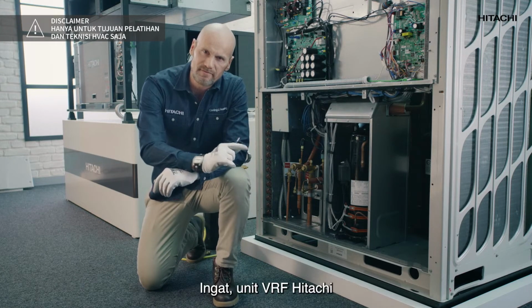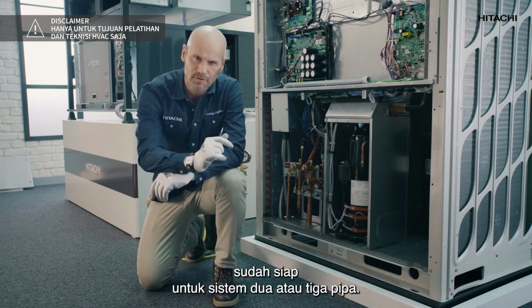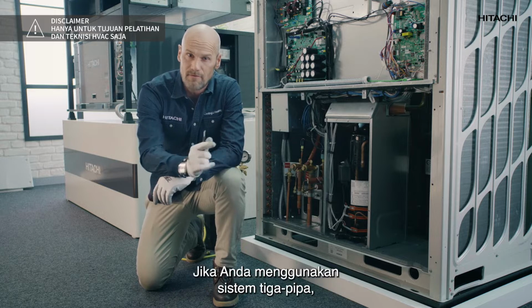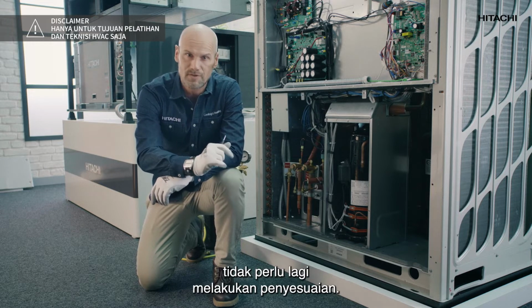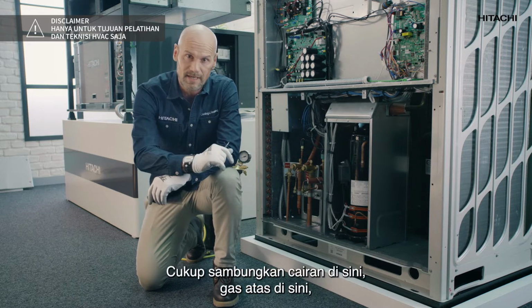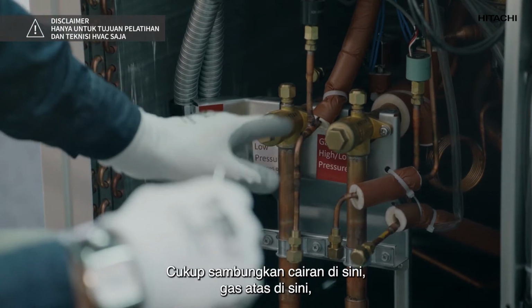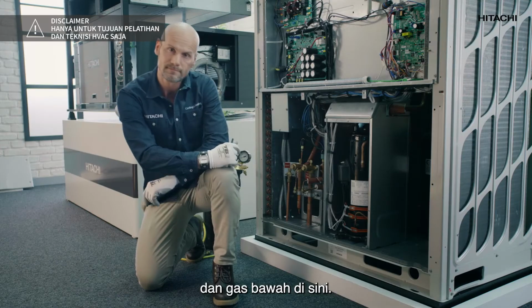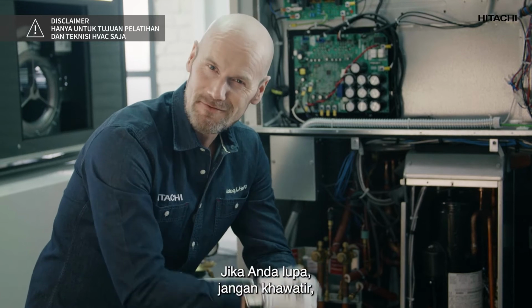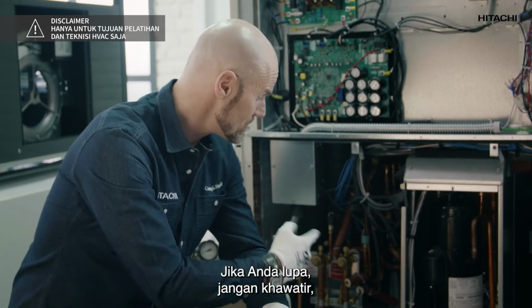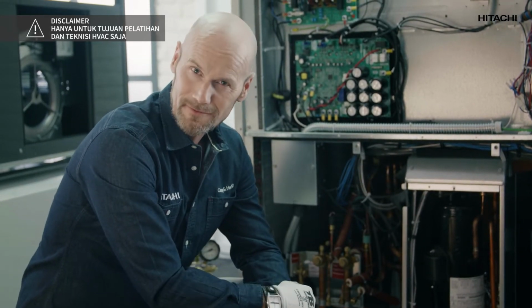Don't forget that Hitachi VRF units are already prepared for 2 or 3 pipe systems. If you have a 3-pipe system, there's no need to make any adjustments. Just connect the liquid here, the high gas here, and the low gas here. If your memory fails you, don't worry. As you can see, all our units are labeled.